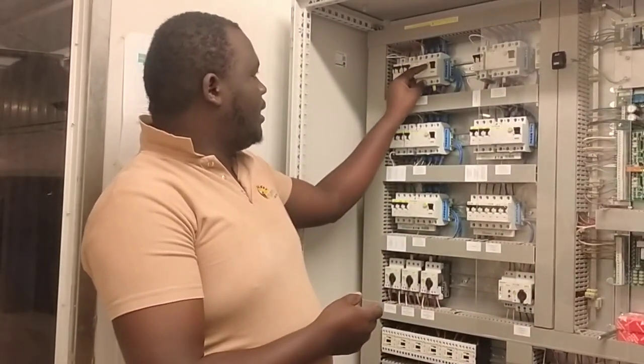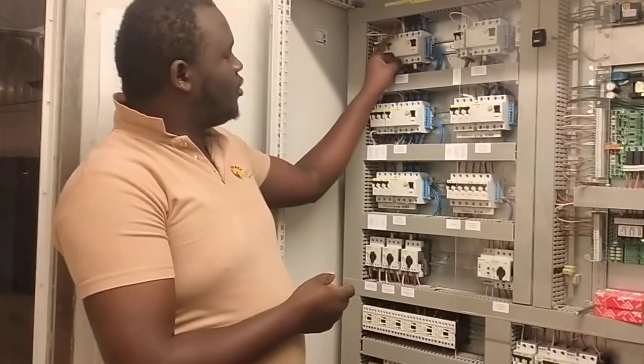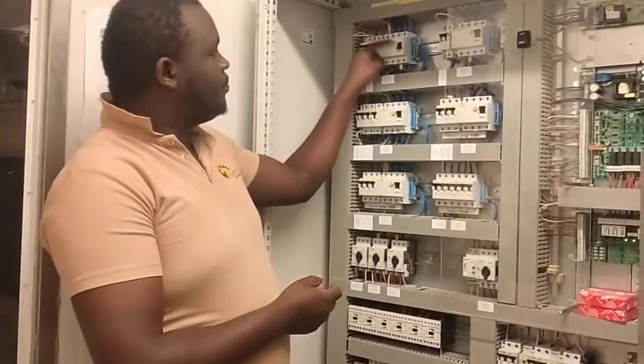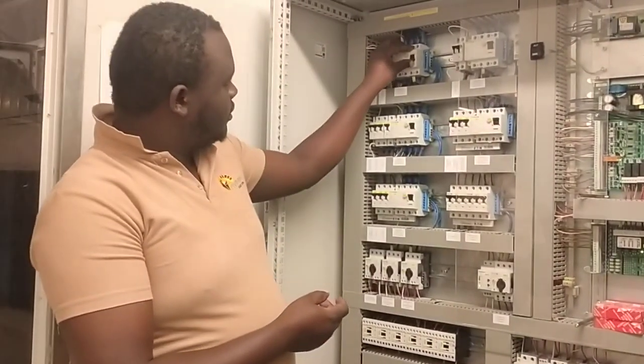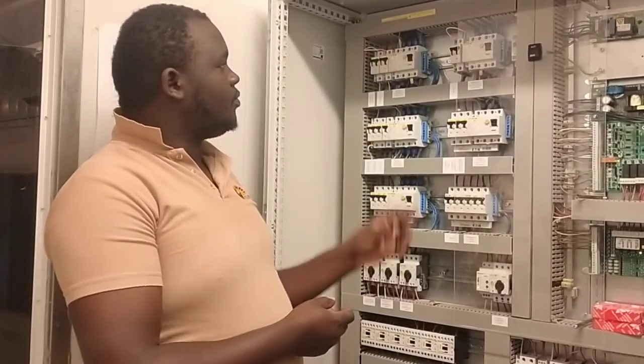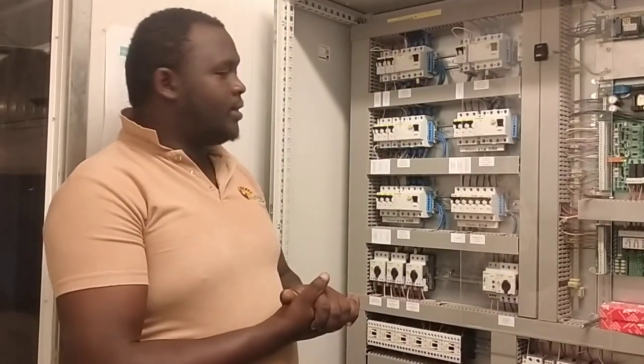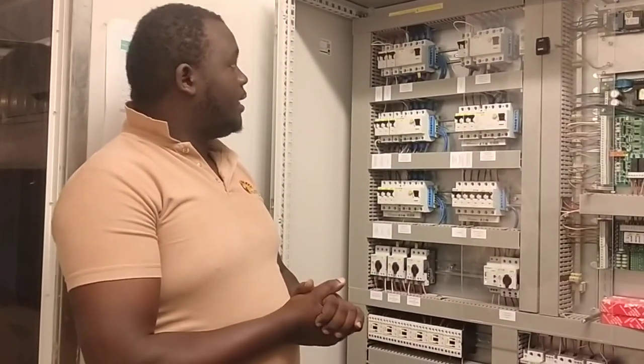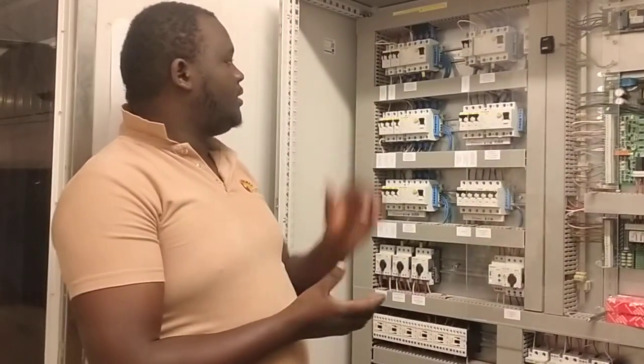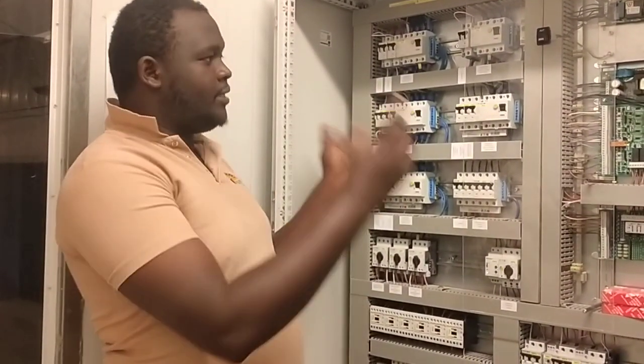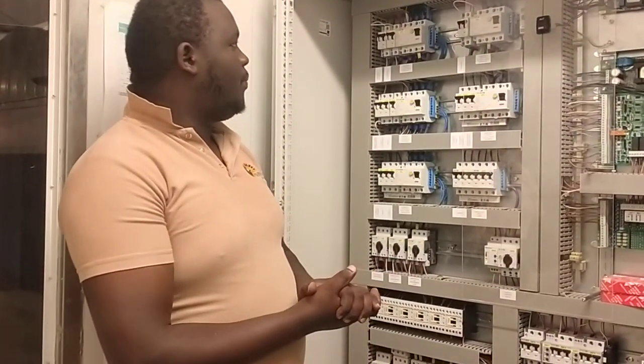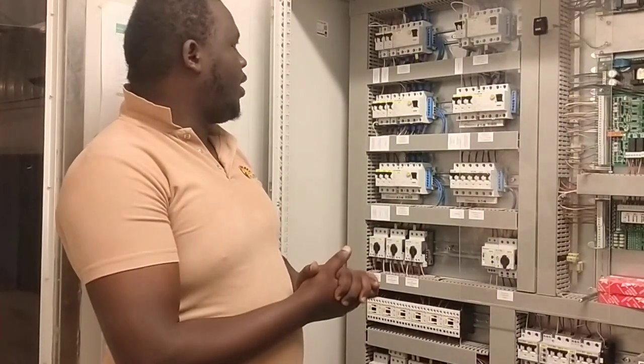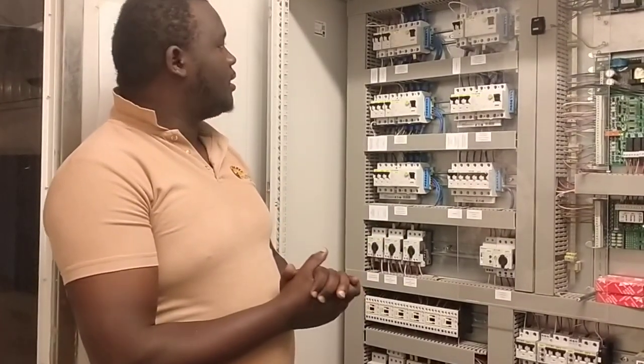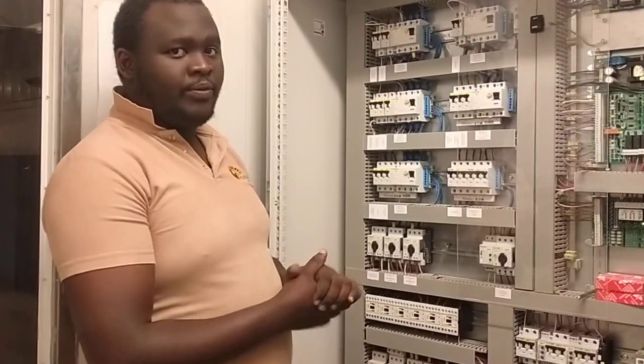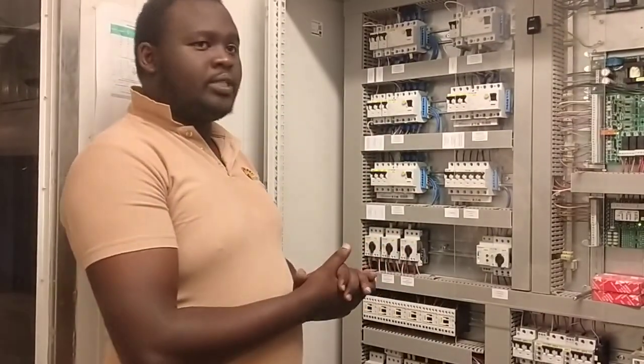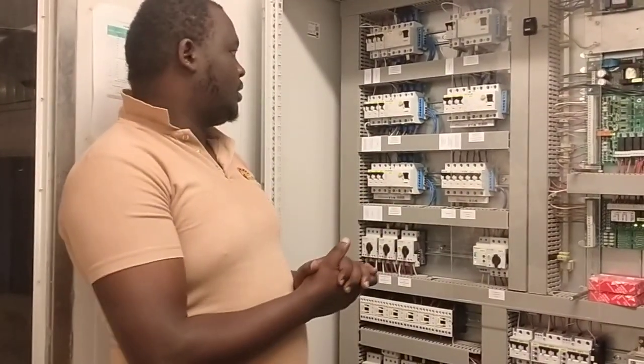So maybe I give you a test. You can see when you want to test this RCD function, that one works. So as an engineer or electrical personnel, it is good to ensure that your RCDs are working. In our case here, we normally do a biannual or sometimes annual checkup of RCDs, that is after commissioning. Before commissioning, it's good you also study this and do all the tests to ensure you have a safe MCC.